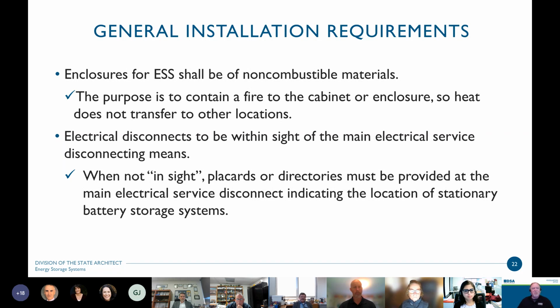So really, when we're talking about that heat transfer and when these things develop or fail, that's really the threat that we're worried about. Adjacent exposures, heat transfer inside the units from one battery array to another. And that's really the purpose of that 9540 testing and listing. They're going to look at that. If an element, a battery array fails, how much heat is generated and is it transferred to the adjacent one? And we're looking to limit or minimize any kind of catastrophic events.